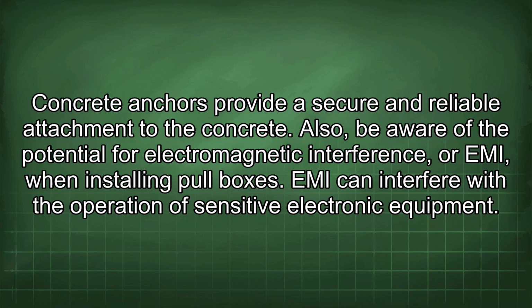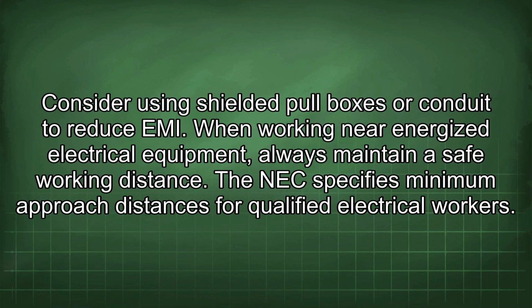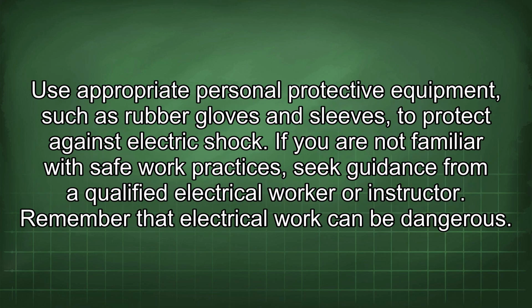Also, be aware of the potential for electromagnetic interference, or EMI, when installing pull boxes. EMI can interfere with the operation of sensitive electronic equipment. Consider using shielded pull boxes or conduit to reduce EMI. When working near energized electrical equipment, always maintain a safe working distance. The NEC specifies minimum approach distances for qualified electrical workers. Use appropriate personal protective equipment, such as rubber gloves and sleeves, to protect against electric shock.